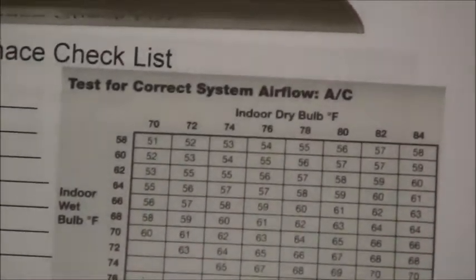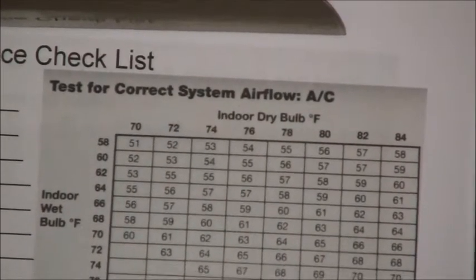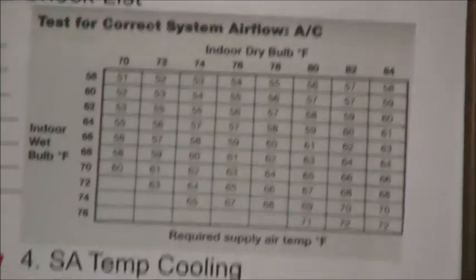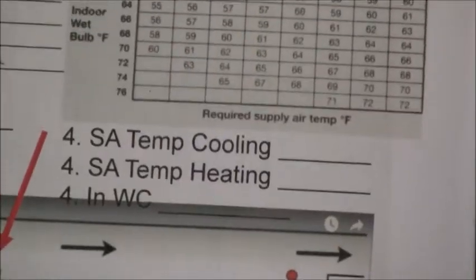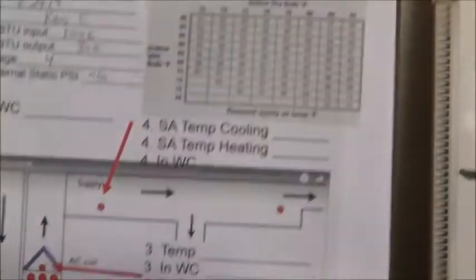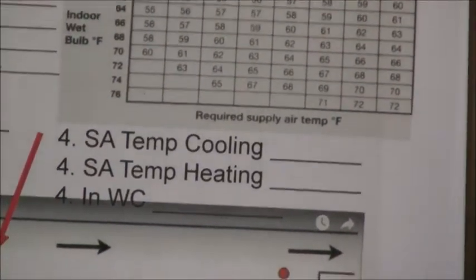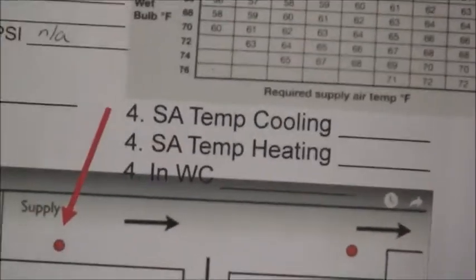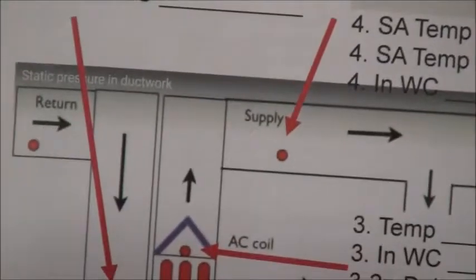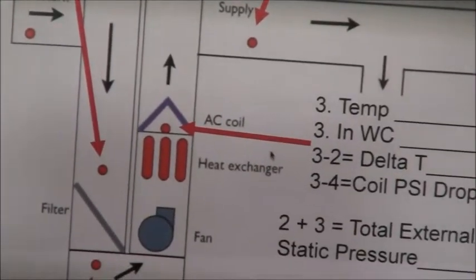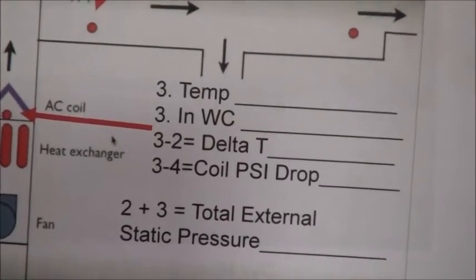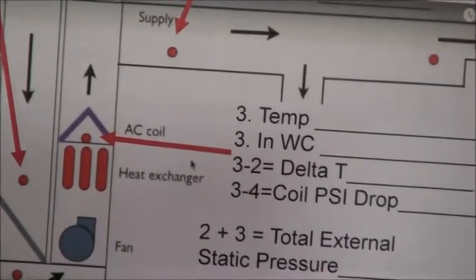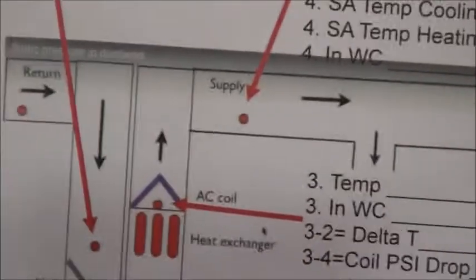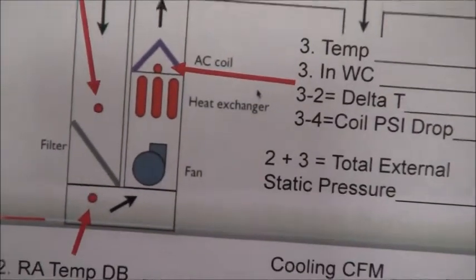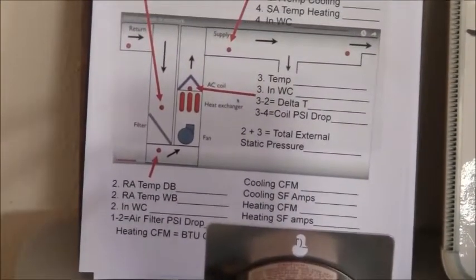Now I do have some formulas here. This is an airflow for AC. We'll go through that so we can get the AC. We're going to get some temperature readings, supply air temperature, cooling and heating, and the inches of water column at sample point 4, which is after the AC coil. We're going to get the delta T, which is the temperature difference, which is point 3, which is that point right there, minus point 2 over there. So we'll go through the whole thing and make sure that you got it 100%.